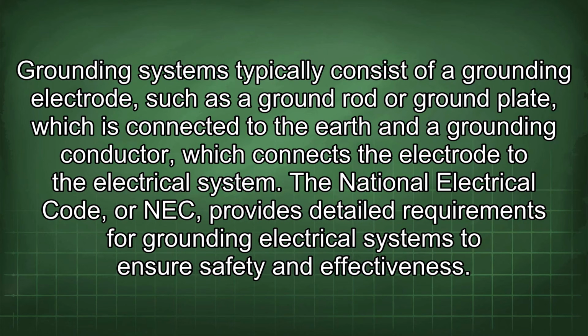Grounding systems typically consist of a grounding electrode, such as a ground rod or ground plate, which is connected to the earth, and a grounding conductor, which connects the electrode to the electrical system. The National Electrical Code, or NEC, provides detailed requirements for grounding electrical systems to ensure safety and effectiveness.